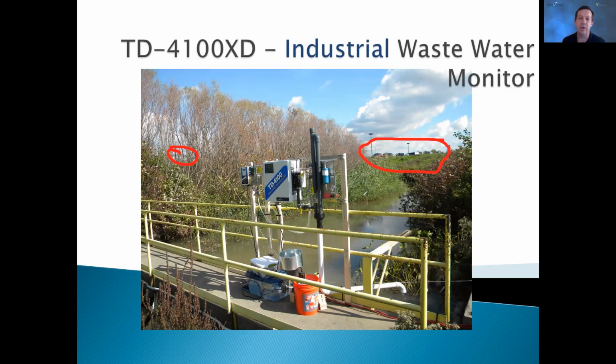This is a demonstration that we put on a couple of years ago for a customer to demonstrate low maintenance operation and high sensitivity. After a month of service in this very dirty, murky, turbid water, this oil water monitor was clean.